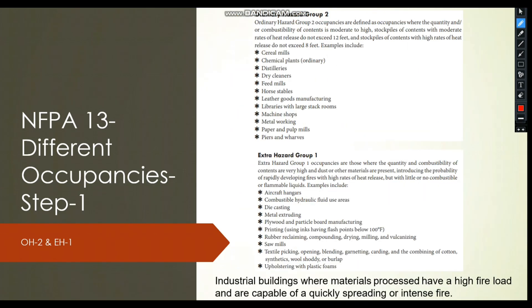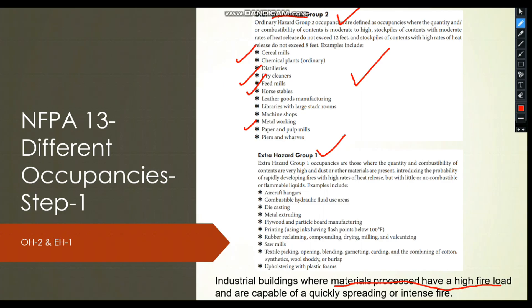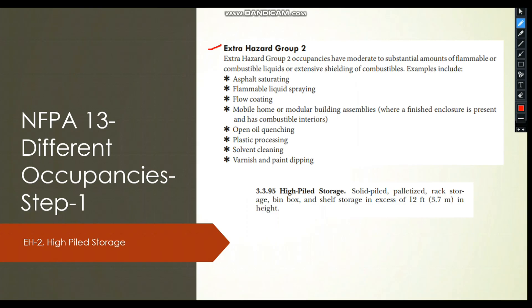Ordinary hazard group 2 includes chemical plants, flour mills, horse stables, and paper and pulp mills. Extra hazard group 1 covers industrial buildings where materials processed have a high fire load with the potential for quickly spreading or intense fire — examples include aircraft hangars, die casting machines, and metal extruding operations. Extra hazard group 2 covers high-spreading fires such as flammable liquid spraying areas and asphalt saturating areas.